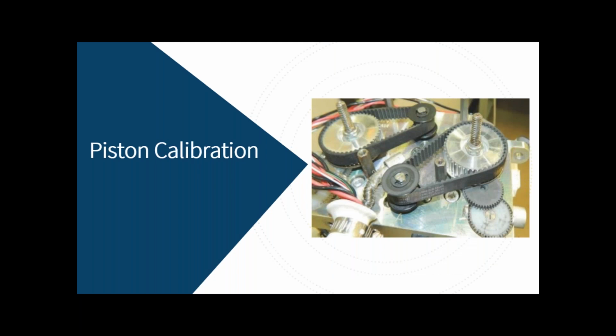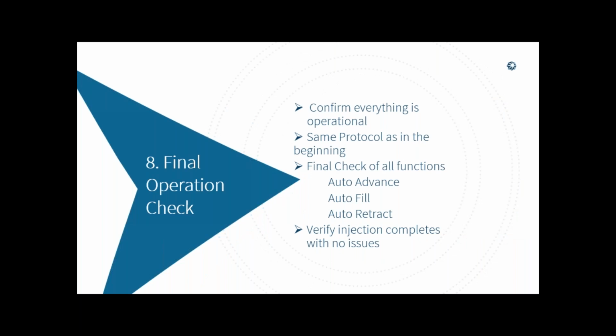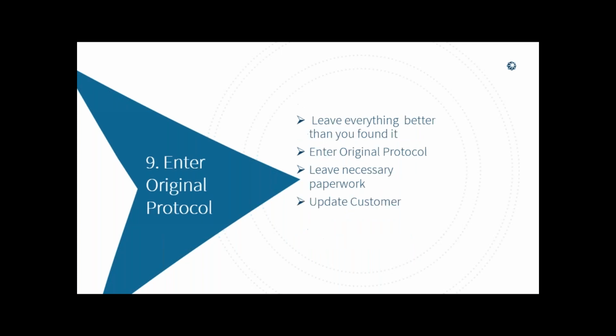Piston calibration is 50 milliliters on the screen, 50 milliliters. There's piston calibrations for these also, which may not be for the IV pump, but there are for this one. So you have to make sure that 0 is 0 and 150 is 150 and so on and so forth. Final operation, confirm everything is operational. Same protocol as in the beginning. Final checks. What same protocol you use at the beginning, you finish up with. And if you have no errors, you can inform the customer of what's going on and update the customer.